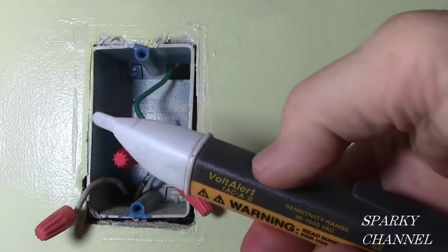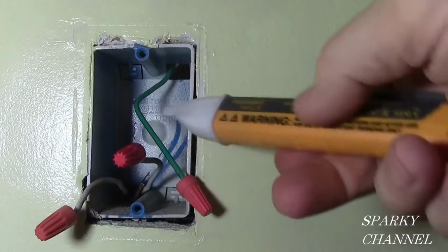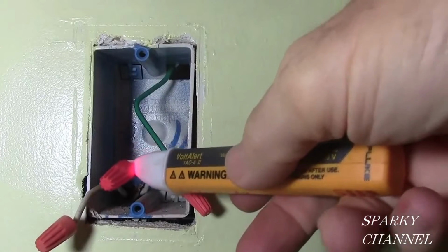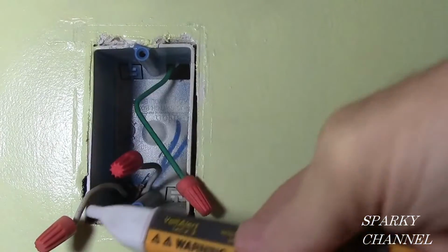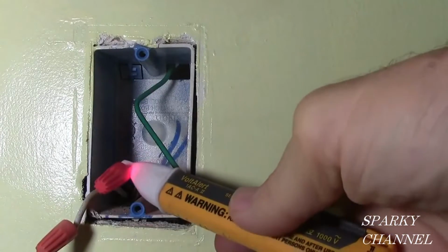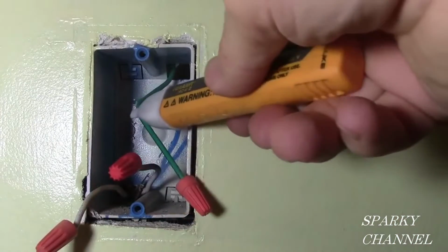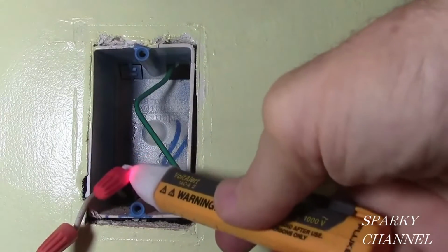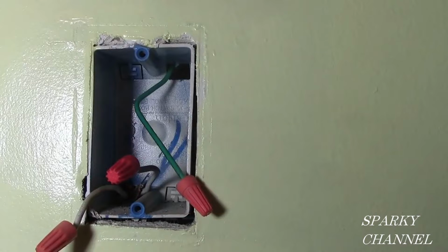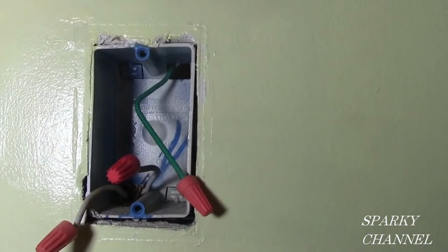What I'm going to do is take my Fluke voltage detector and test the wires and find out which one is hot. See, the black wire is hot, the white wire isn't, and the ground wire isn't. The black wire that is beeping is called the line wire. You need to know which one is the line wire to install an occupancy sensor switch.